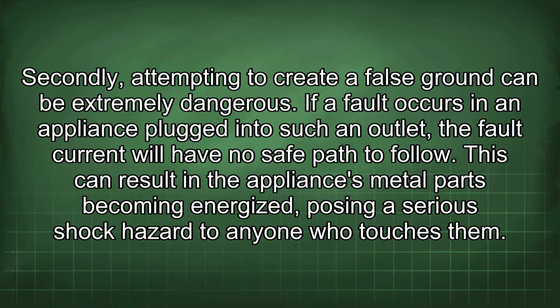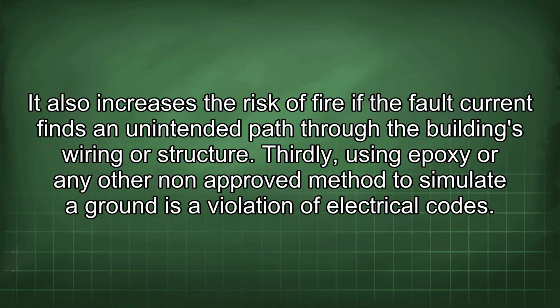Secondly, attempting to create a false ground can be extremely dangerous. If a fault occurs in an appliance plugged into such an outlet, the fault current will have no safe path to follow. This can result in the appliance's metal parts becoming energized, posing a serious shock hazard to anyone who touches them. It also increases the risk of fire if the fault current finds an unintended path through the building's wiring or structure.